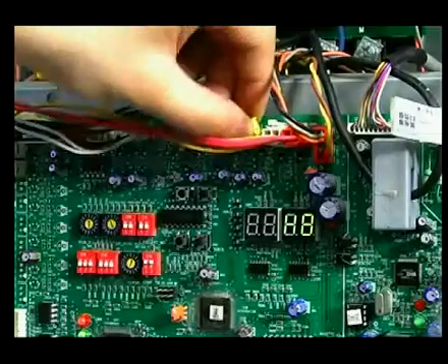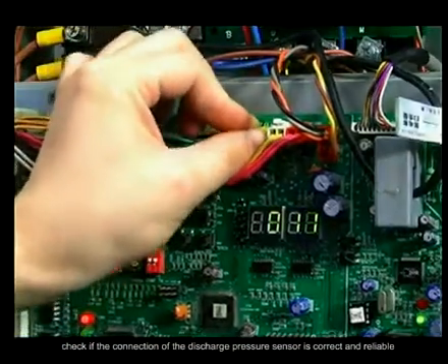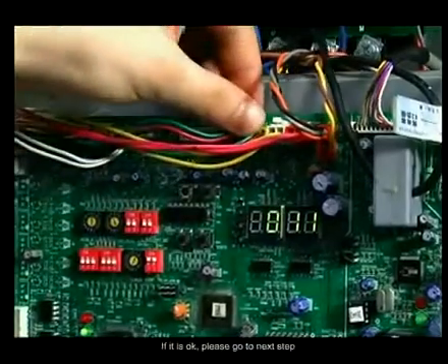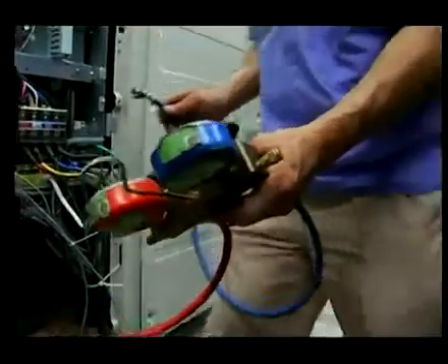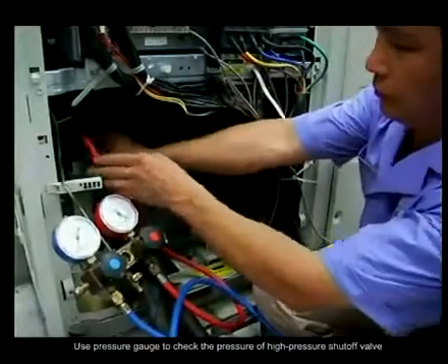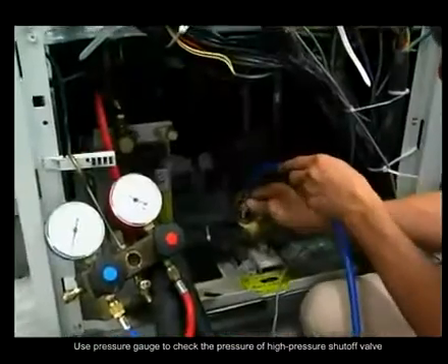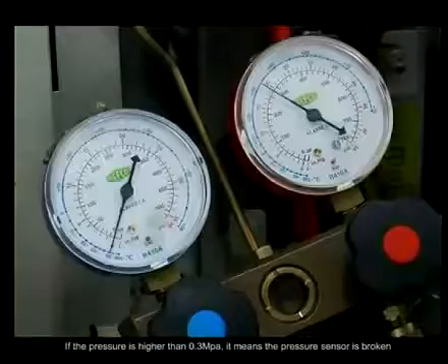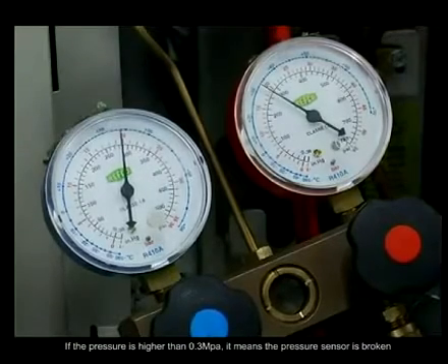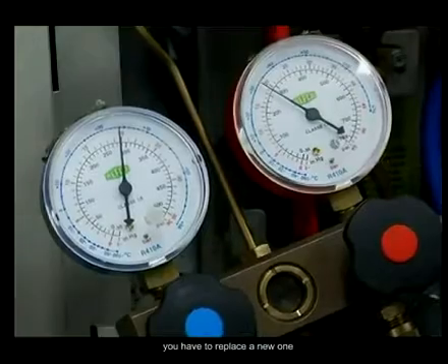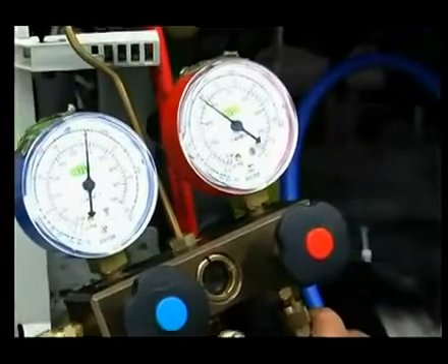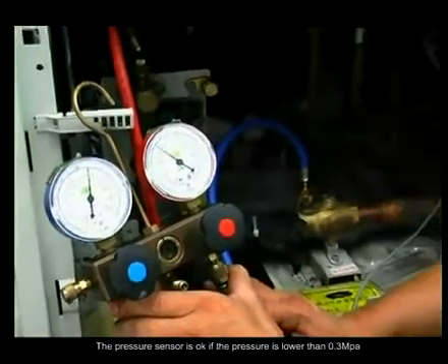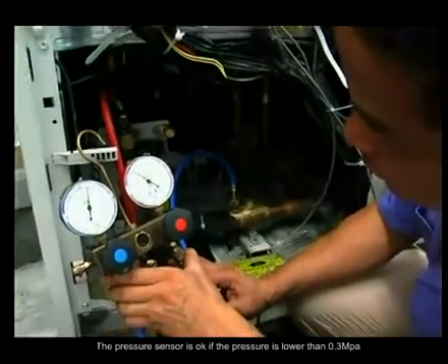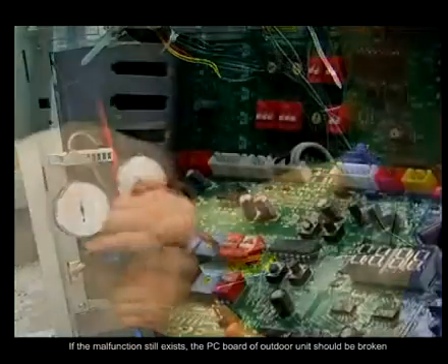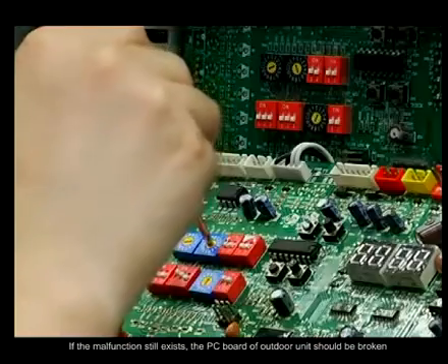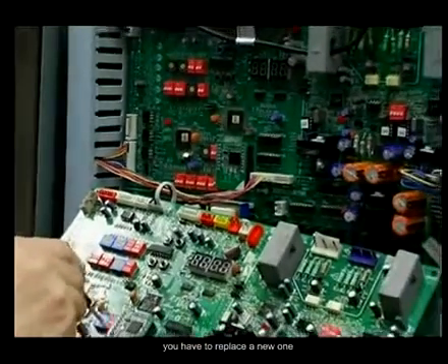Step 1. Check if the connection of the discharge pressure sensor is correct and reliable. If it is okay, please go to the next step. Step 2. Use a pressure gauge to check the pressure of the high pressure shutoff valve. If the pressure is higher than 0.3 MPa, it means the pressure sensor is broken. You have to replace a new one. The pressure sensor is okay if the pressure is lower than 0.3 MPa. If the malfunction still exists, the PC board of the outdoor unit should be broken. You have to replace a new one.